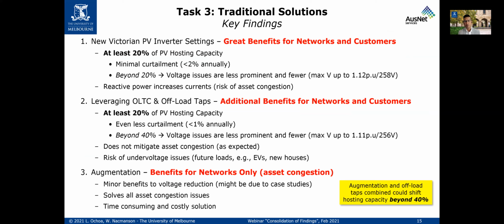First of all, we modeled in all the solutions the Victorian, we keep calling them the new Victorian settings, but actually they're not that new now, because that was in December 2019 that they started being used, or in effect perhaps January 2020, so more than a year ago. These settings essentially require not just volt-watt settings, which naturally implies curtailment, but simultaneously the volt-var settings, so the combination of reactive power with management of active power according to certain voltage points.